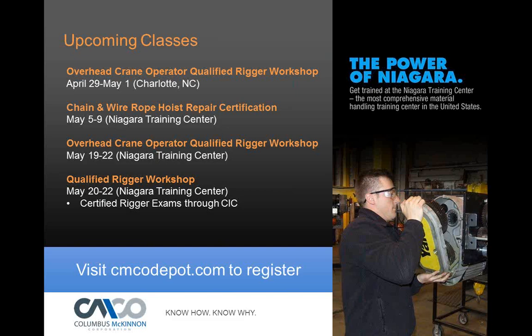Excellent. Thank you. I'd like to make another point there. If I had a standard hoist that I think I'm going to move into a hazardous location, I would not try to modify that hoist on my own and put spark-resistant features on there. There are certain things that we do, especially in chain hoists, to accept some spark-resistant features, such as if we're going to do stainless steel chain, we do put special lift wheels in so that we don't chew the chain up and things of that nature. So don't just take it upon yourself to convert something over that you feel will be spark resistant. You need to call the original manufacturer and ask what needs to be done.